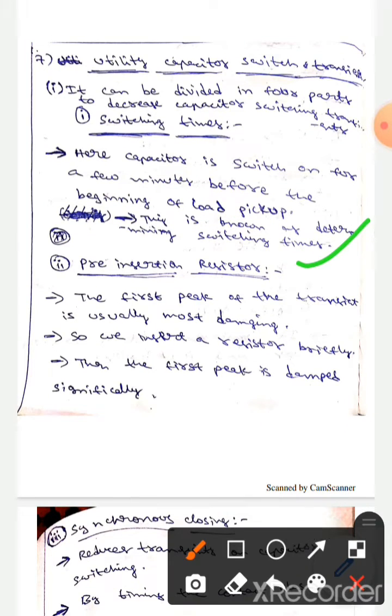The next one is pre-insertion resistor. Here the first peak of the transients is usually most damaging, so we insert a resistor briefly. Then the first peak is damped significantly.